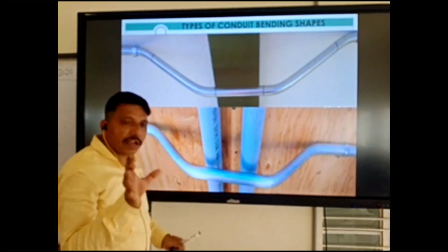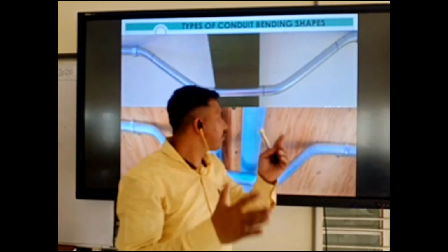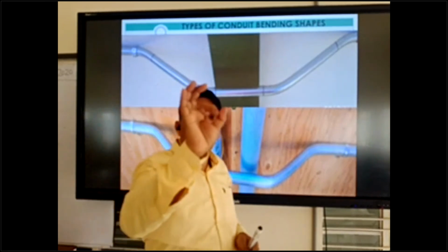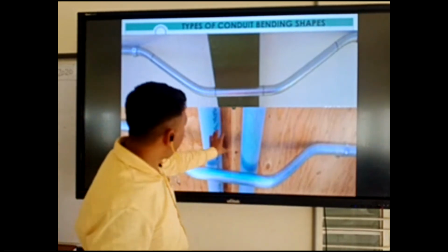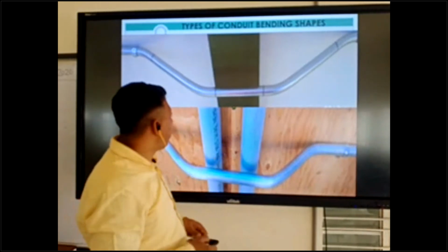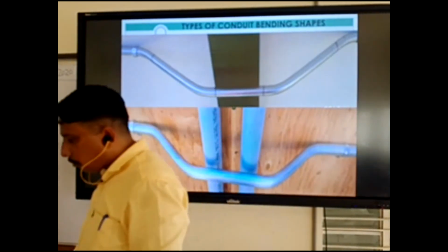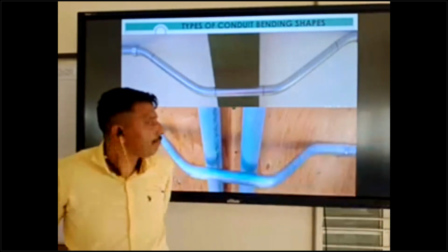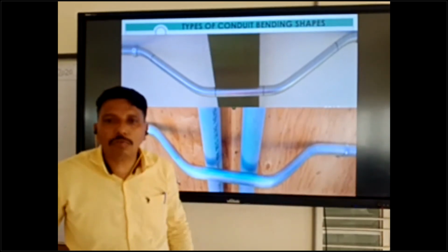Then you check the distance. If the width is only 10 centimeters and only a small electrical pipe is crossing, you can use a small bridge. But for something like a drainage pipe, water or firefighting pipe, or a beam, you use a long bridge. Okay, so clear about this one. I hope it is clear.